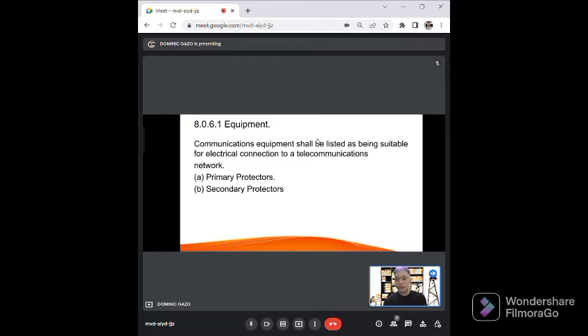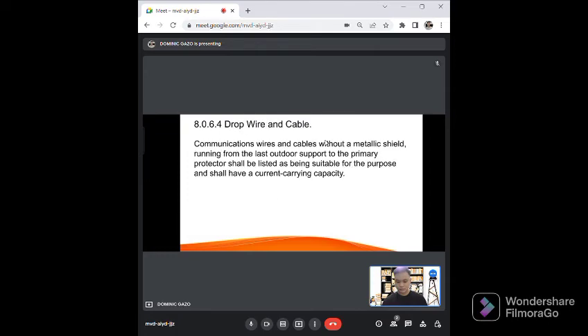And then for secondary protectors, this secondary protector shall be listed as suitable to provide a means to safely limit currents to less than the current carrying capacity. And then for drop wire and cable, communications wires and cables without a metallic shield running from the last outdoor support to a primary protector shall be listed as being suitable for the purpose and shall have current carrying capacity.